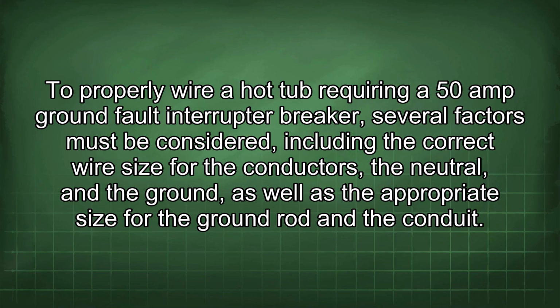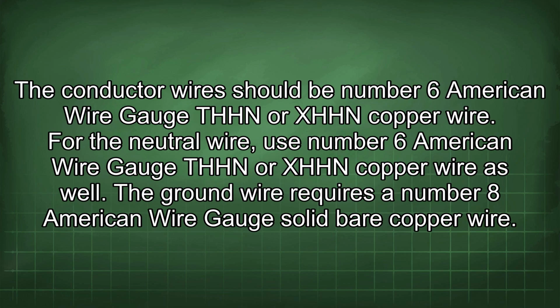To properly wire a hot tub requiring a 50 amp ground fault interrupter breaker, several factors must be considered, including the correct wire size for the conductors, the neutral, and the ground, as well as the appropriate size for the ground rod and the conduit. The conductor wires should be number 6 American wire gauge THHN or XHHN copper wire. For the neutral wire, use number 6 American wire gauge THHN or XHHN copper wire as well. The ground wire requires a number 8 American wire gauge solid bare copper wire.